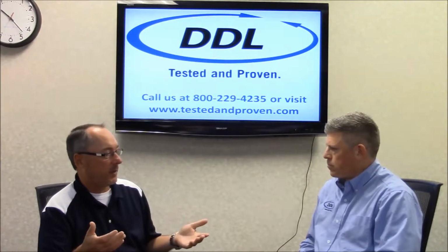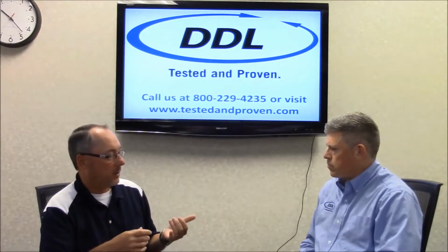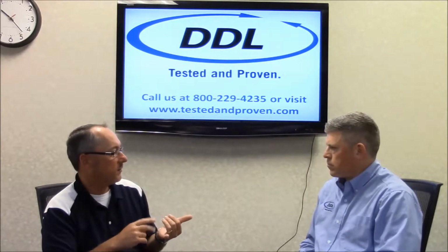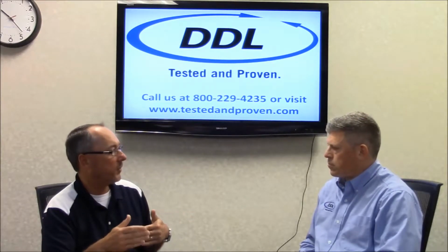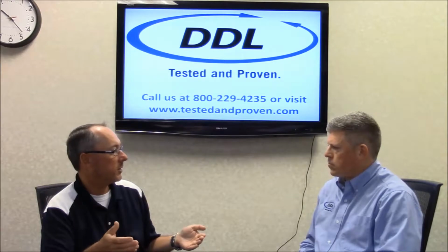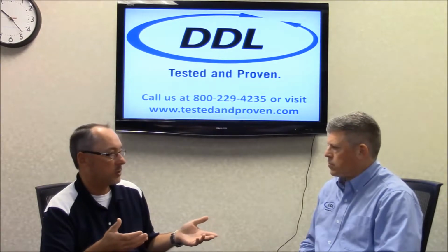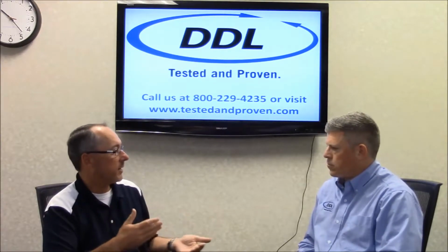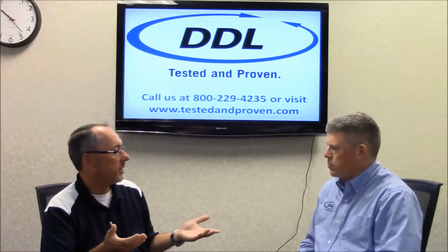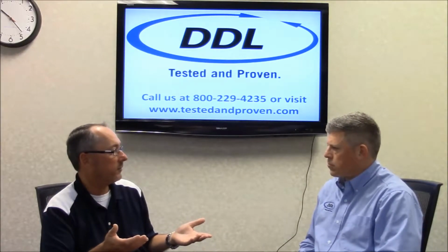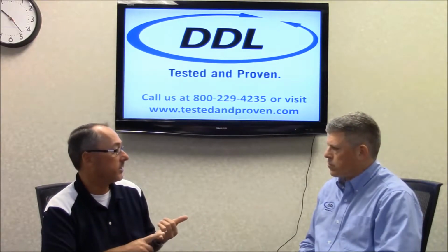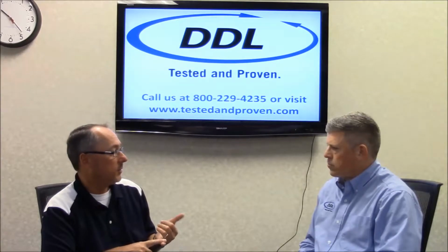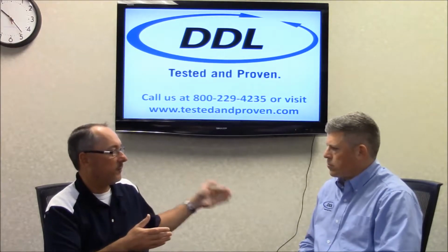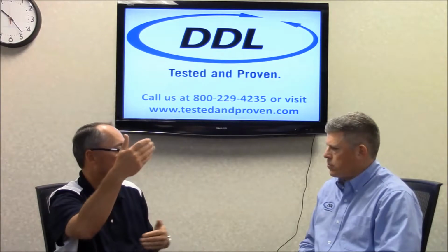So for package validation after accelerated aging, you're going to execute your physical strength testing, your physical integrity testing to prove out that no adverse effects from aging has caused a sterility breach in the package. On the flip side, if it's product testing, well then you're going to take your product and go through your whole battery of tests that you would have done at T0 or your baseline to ensure that aging hasn't caused adverse effects, and then compare those results back up.